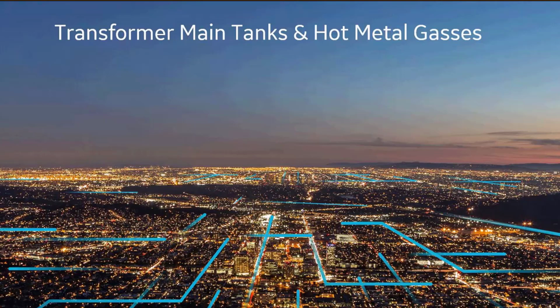And that's how oftentimes we determined whether or not there was an internal fault. If the gases were high, had gone up on the transformer—the percent fault gas—well, then we would obviously start doing some offline diagnostic testing to try to sort out where the problem was.